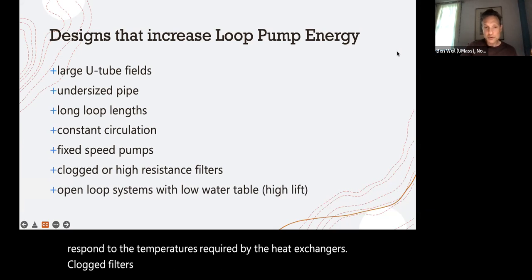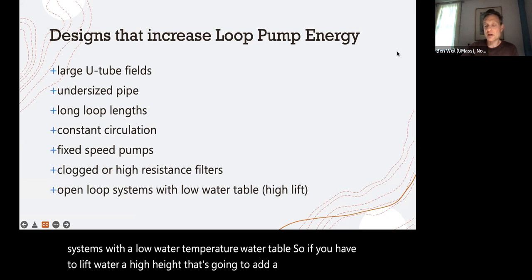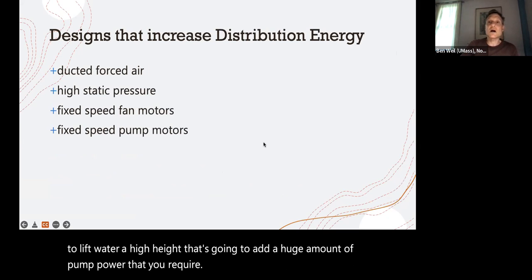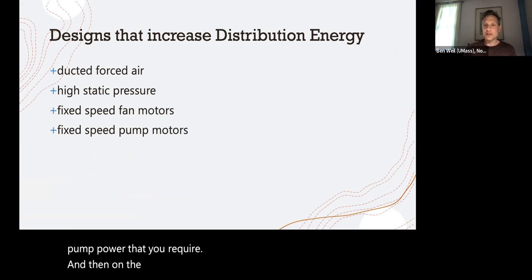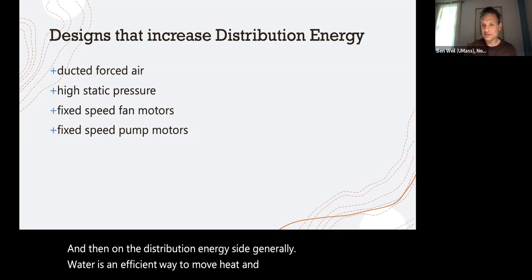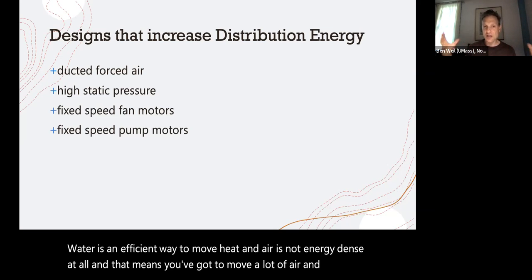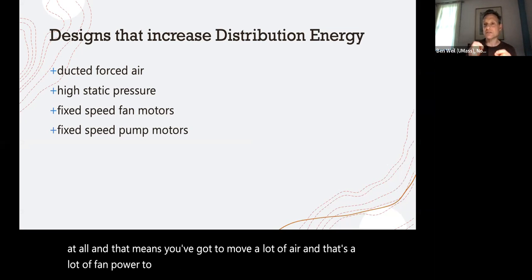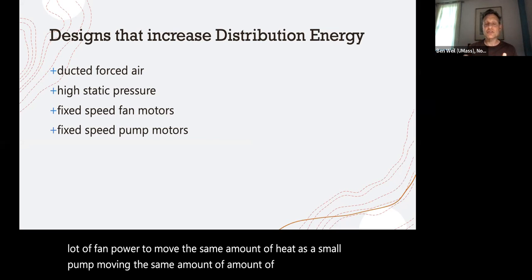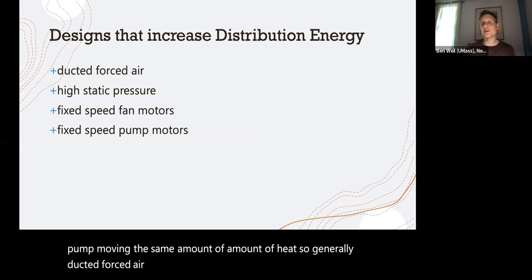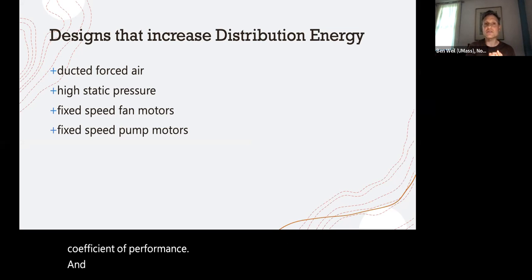Clogged filters, so this is for open loop systems, and open loop systems with a low water table. If you have to lift water a high height, that's going to add a huge amount of pump power that you require. And then on the distribution energy side, generally, water is an efficient way to move heat, and air is not energy dense at all. And that means you've got to move a lot of air, and that's a lot of fan power to move the same amount of heat as a small pump. So generally, ducted forced air systems have a fairly large penalty to their system coefficient of performance. And with those ducted systems, high static pressure is going to increase your fan energy required.